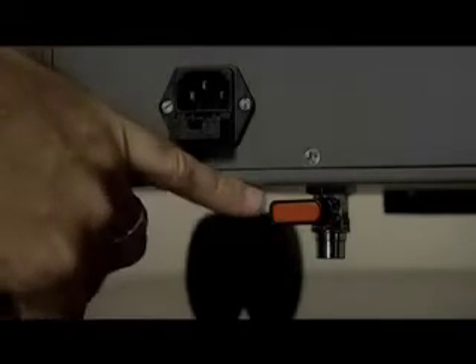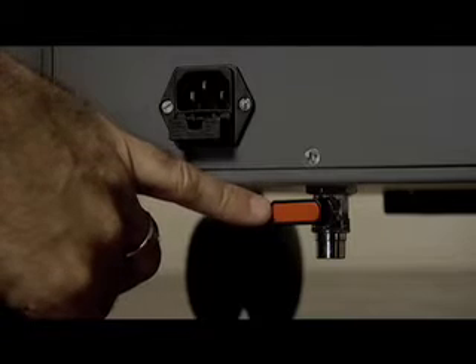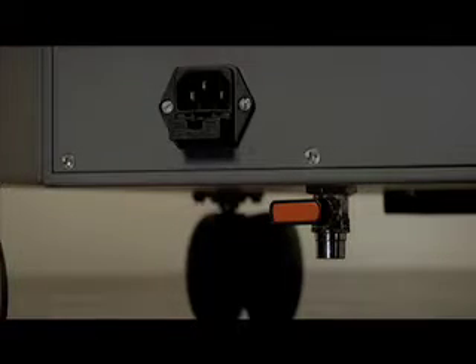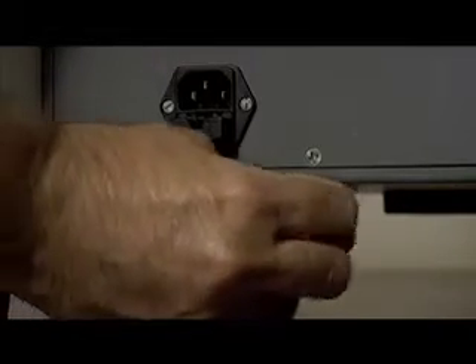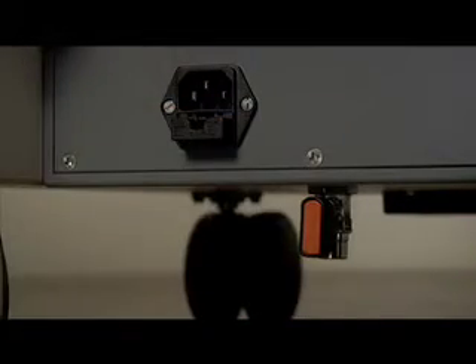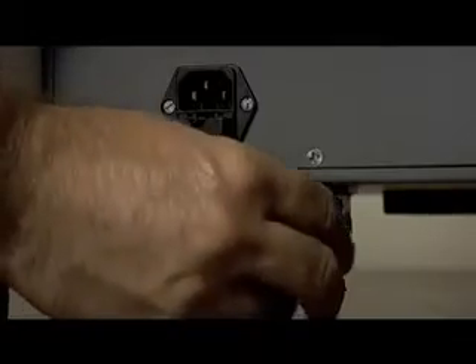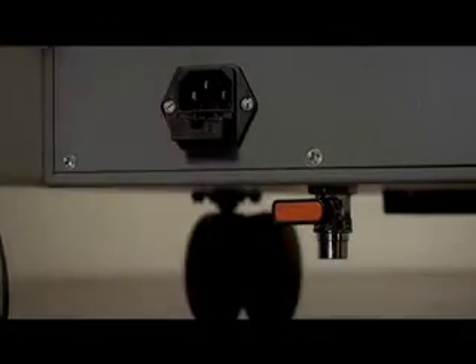At the very end of every case, you must release the air that is compressed inside the system. To release the compressed air, simply turn the red valve at the very bottom of the back of the unit to the right. After the air is released, turn the valve to the left to close so that you are ready for the next case.